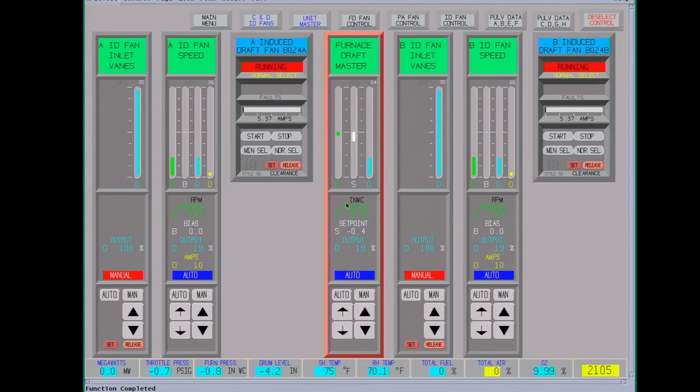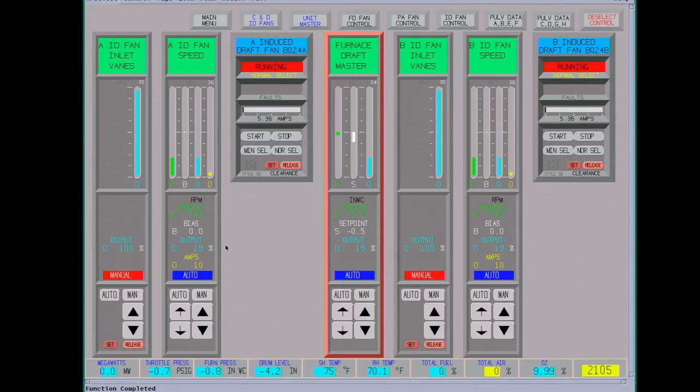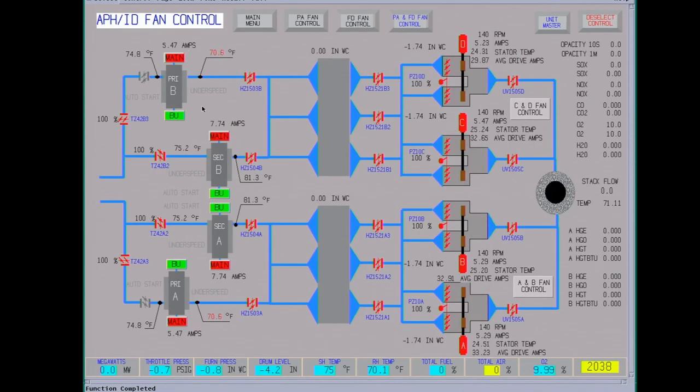Here's your set point, here's your process variable. This is your output. This output runs all four fans, it's split between all four fans. You can bias your fans if you have one that's pulling too much current. You can change the bias and slow it down or speed it up. That's useful when running full load and your air preheaters start plugging, or just other conditions. So you can bias the speed on these fans. You have to watch your current, drive current amps.